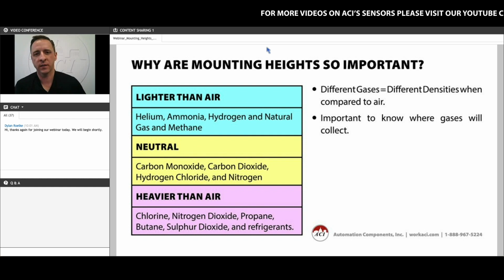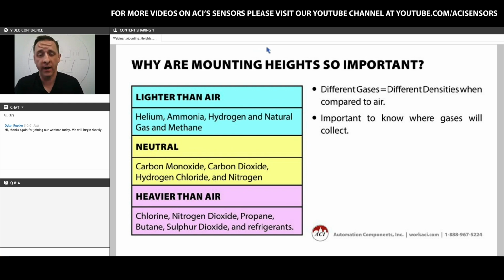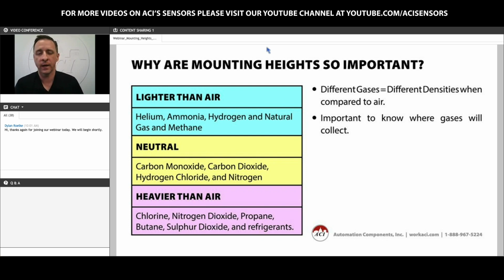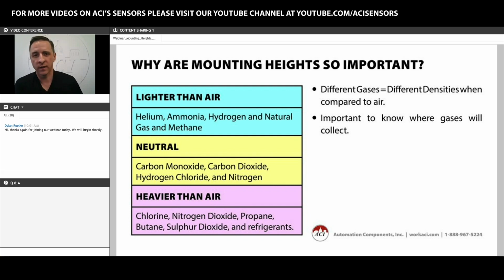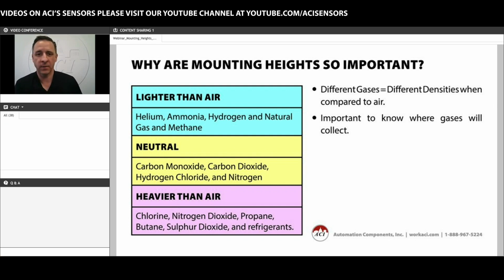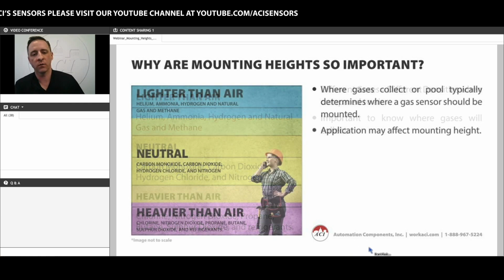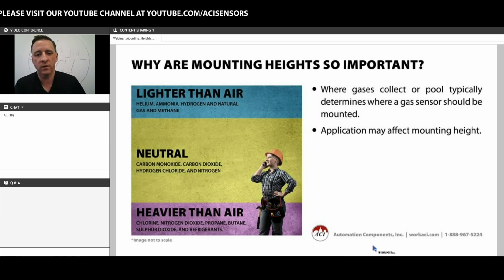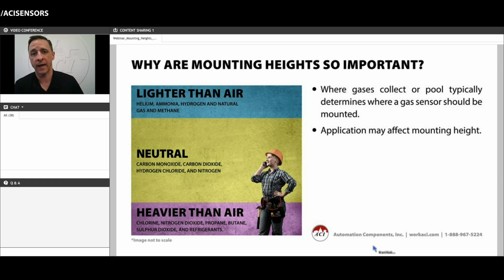We base our gas sensor mounting height recommendations on the specific chemical weight or density of that gas. There are certain gases that are lighter than air, certain gases that are more or less neutral, or the same weight or density as the ambient air, and then there are some gases that are heavier than the ambient air and will sink to the floor. Some examples of these lighter than air gases are helium, ammonia, hydrogen, natural gas, and methane. Because these are lighter or less dense than the ambient air, they will rise to the ceiling of a certain space. And so for those sensors, we would recommend mounting the unit as high towards the ceiling as possible. Generally, that's 6 to 18 inches below the ceiling.